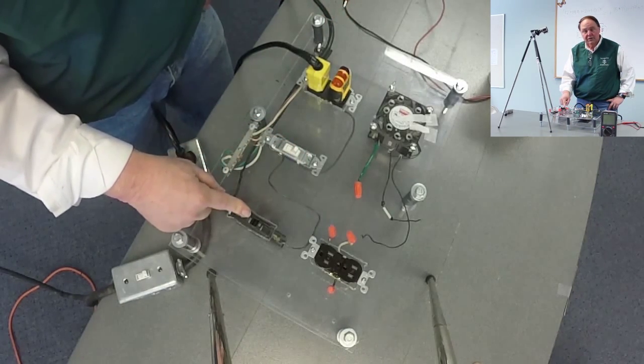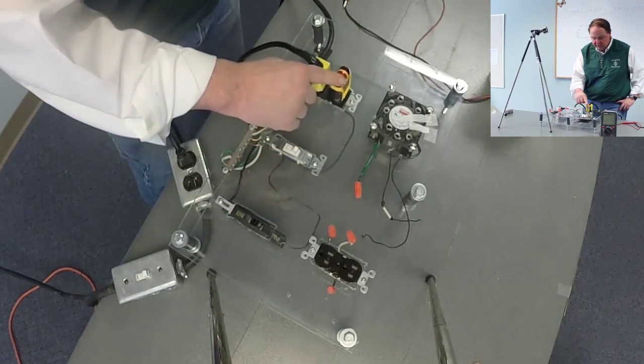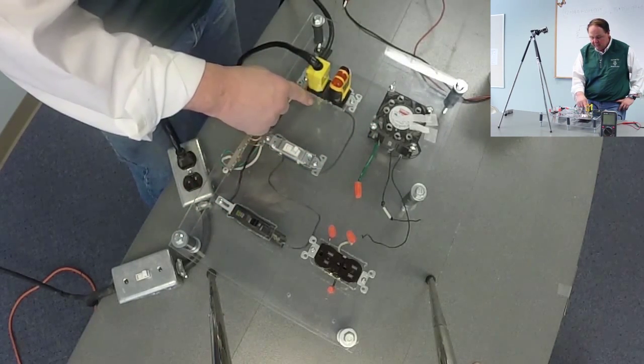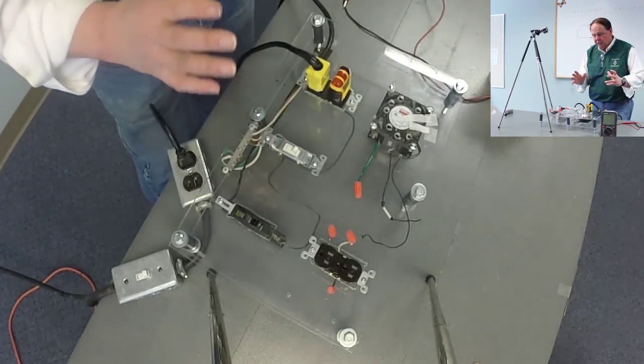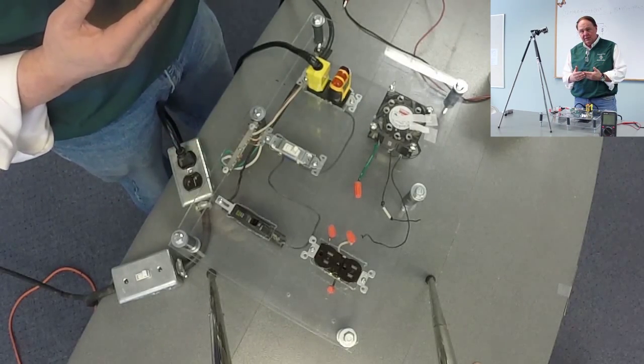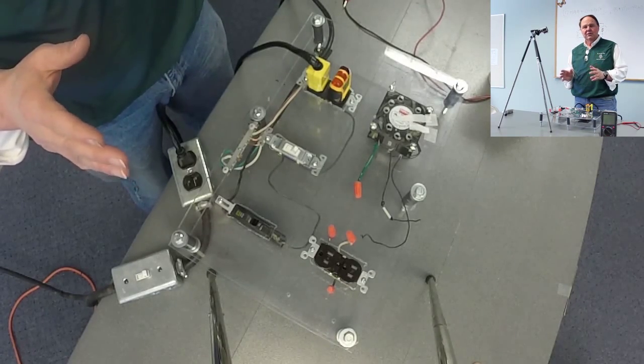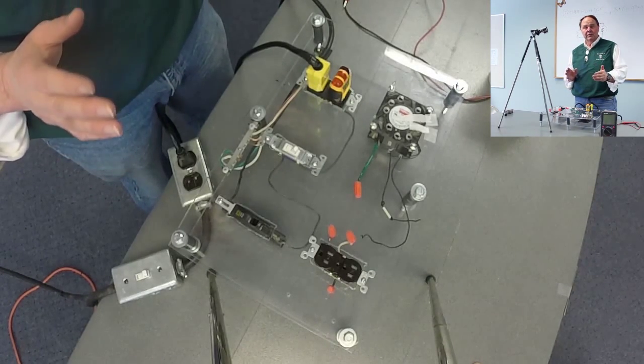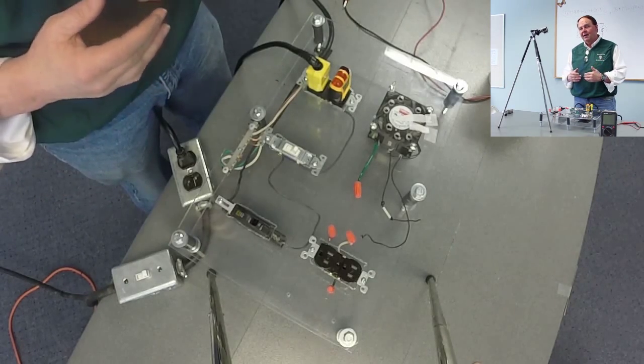From the circuit breaker we're going to this receptacle, and from the receptacle we're going to go to this fan. We'll show you how that works in a few minutes. Keep in mind, the equipment ground must be isolated on the secondary side of the overcurrent protection. That's very important.